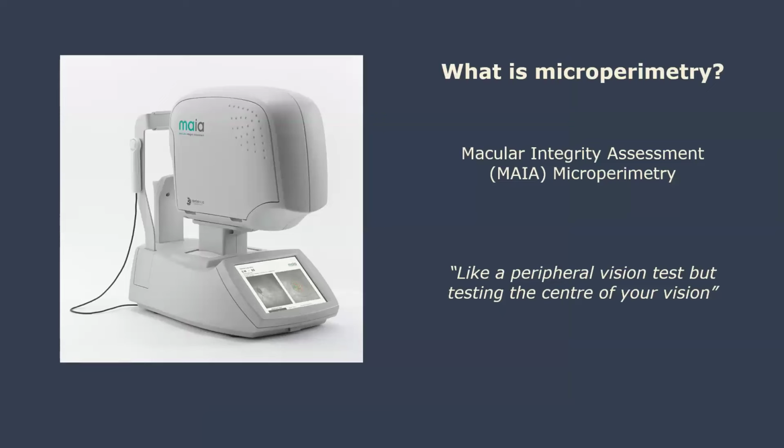There is microperimetry, which is basically like a visual field test, but a much more advanced one that's come out more recently, in the last 10 or 15 years or so. And this incorporates a visual field test, so the flashing dot test, but with a fundus camera, which has automatic eye tracking. So it really takes care of some of the errors we were finding with the old visual fields, that your eye could wander and you wouldn't know if the patient's eyes were wandering all over the place, and that was giving you a false reading. This one will actually log where the patient is looking and compensate for that.